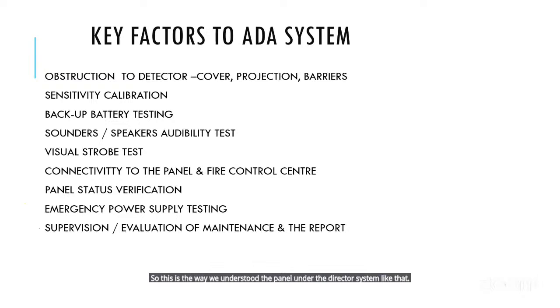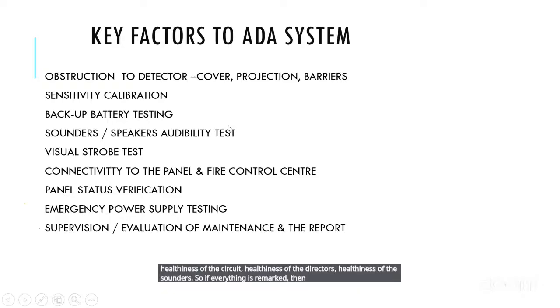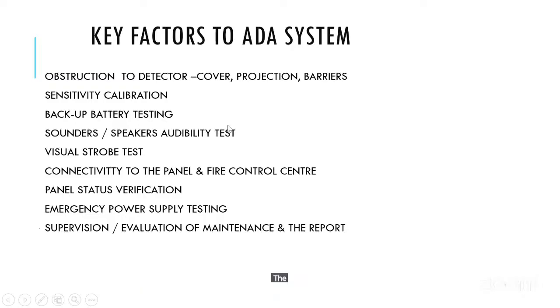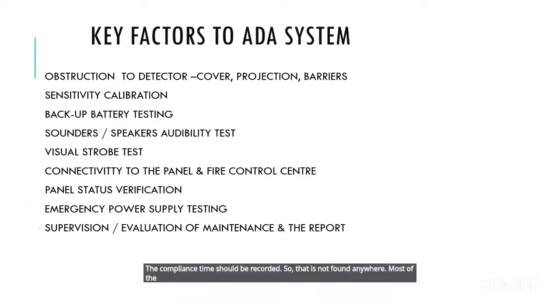So the detector panel is a very sensitive item that will communicate to you the healthiness of the circuit, the healthiness of the detectors, the healthiness of the sounders. So if anything is remarked, then that must be attended to immediately, and that must be recorded immediately. The compliance time should be recorded. That is not found anywhere. In most of the places I could see that it's not available.